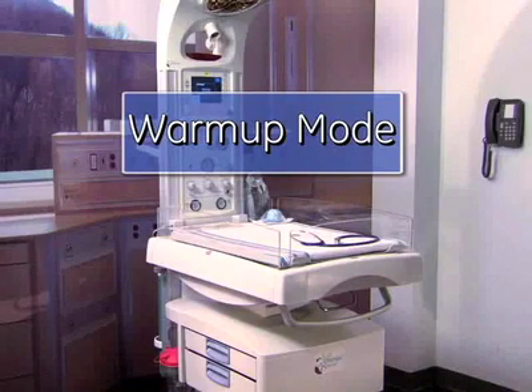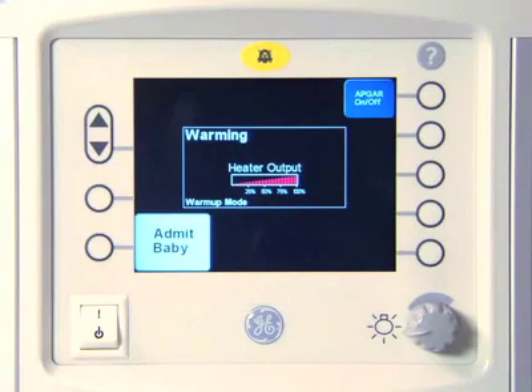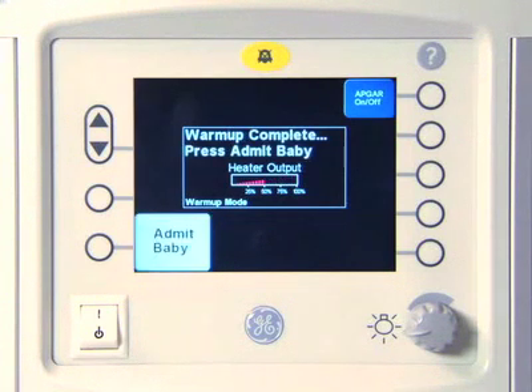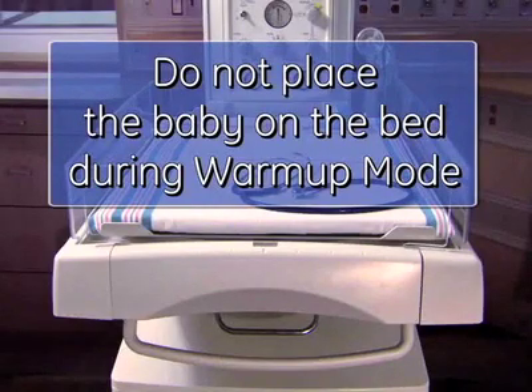Warm-up mode starts immediately upon power on. It lasts for 7 minutes with heater output of 100%. After 7 minutes, heater output drops to 50%. There are no alarms in warm-up mode. Do not place the baby on the bed during warm-up mode.